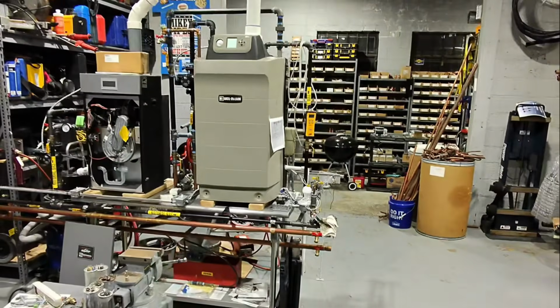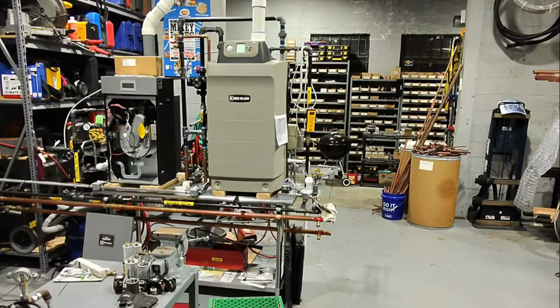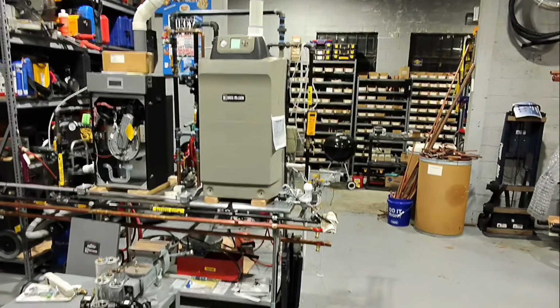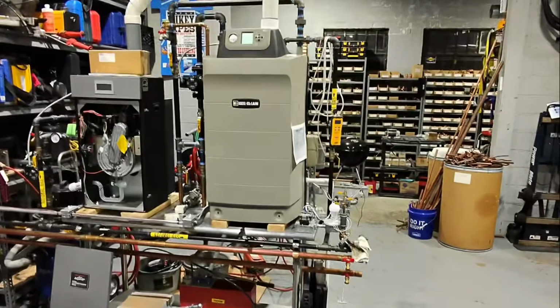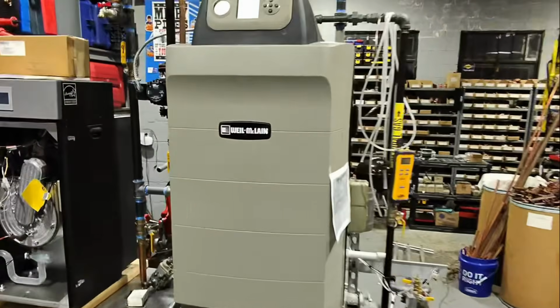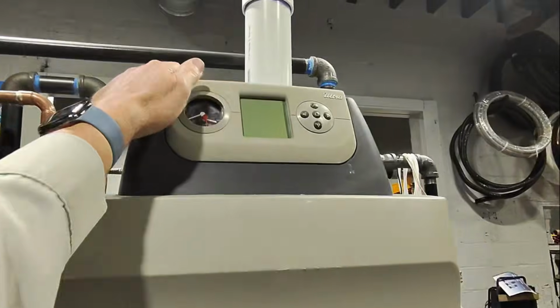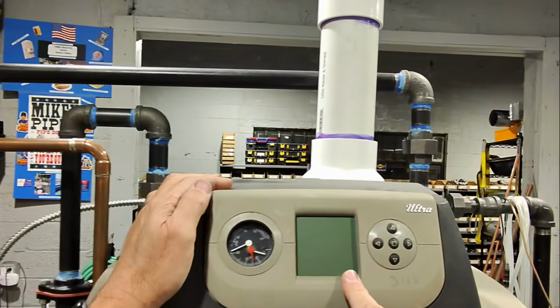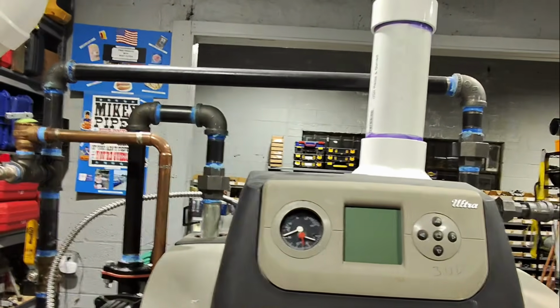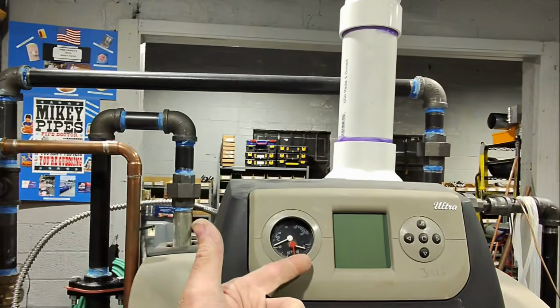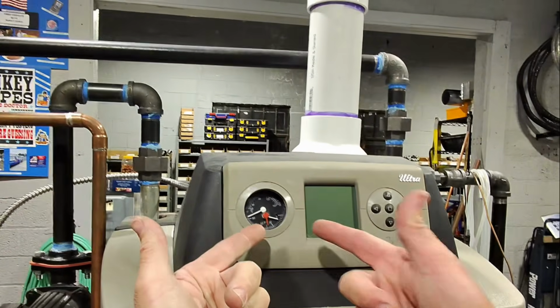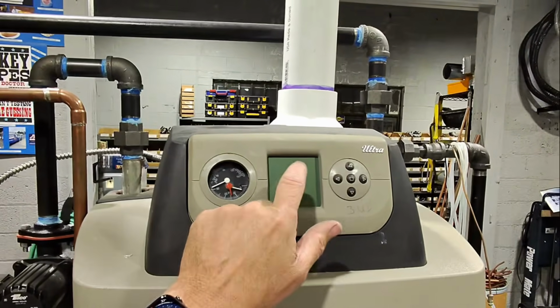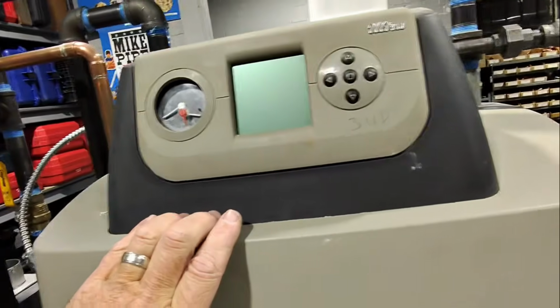So in our Mikey Pipes Philanthropy HVAC training facility, we have the Weil McLain Ultra 3. I believe this is the 299 model, but right now the display is blank. My temperature is non-existent. My pressure is reading roughly where it should be, around 12 psi, but my display is blank. We're going to take the front cover off, take a peek under the hood.